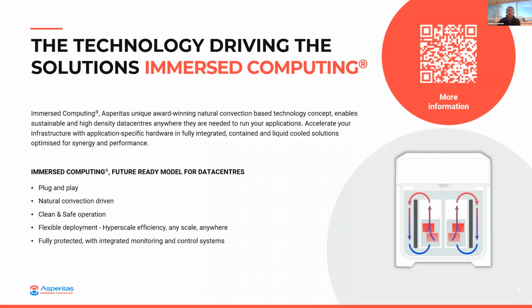So the hot components are driving the flow. That means we don't have to bring the flow to the places where it needs to be cooled, but really we take the flow from where it's being generated. It can't be more efficient than that. There are some advantages to that as well.